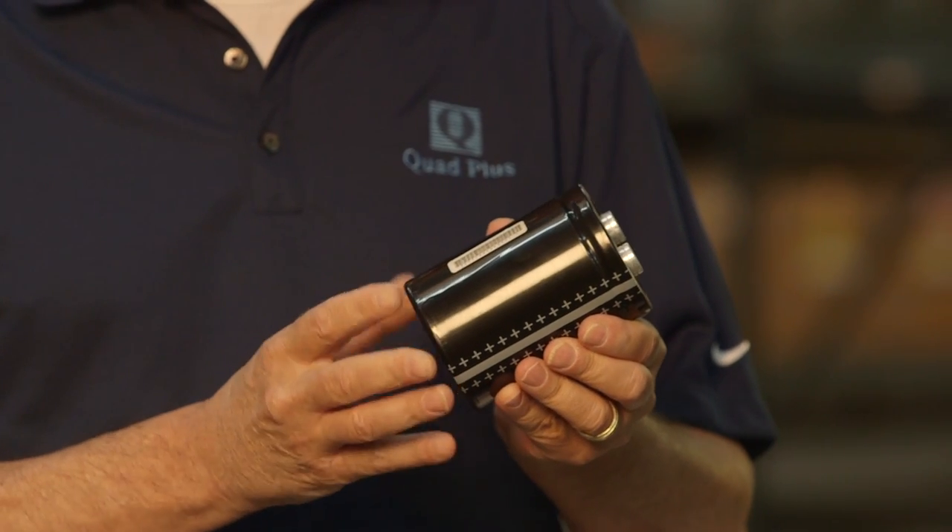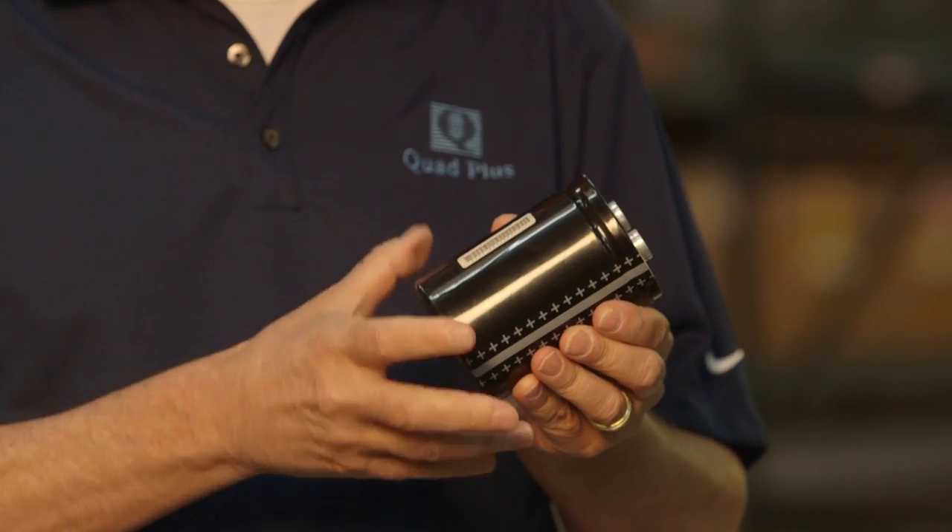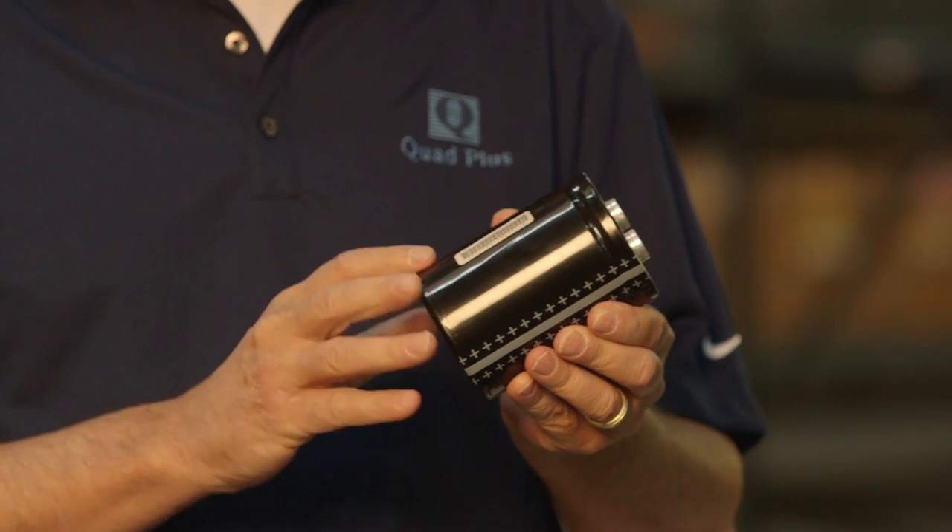The majority of low voltage AC drives on the market today have electrolytic capacitors installed for DC bus filtering. These capacitors come in various lengths, various diameters, and colors. The range of values is anywhere from 5,000 microfarads to 10,000 microfarads, and 400 volts to 500 volts.